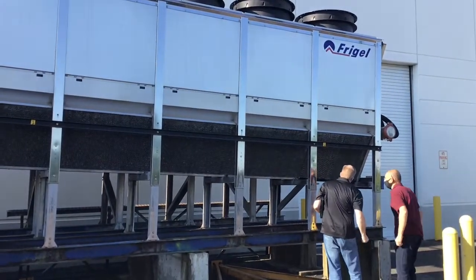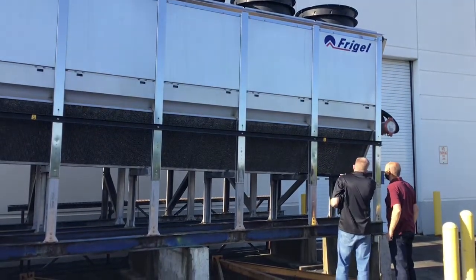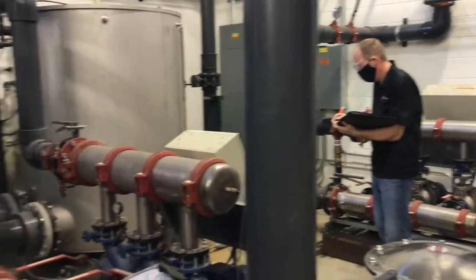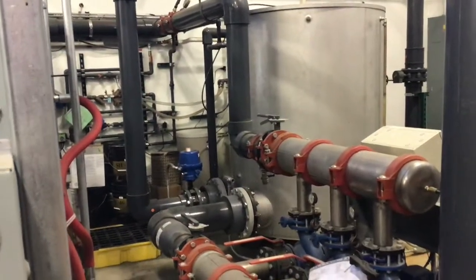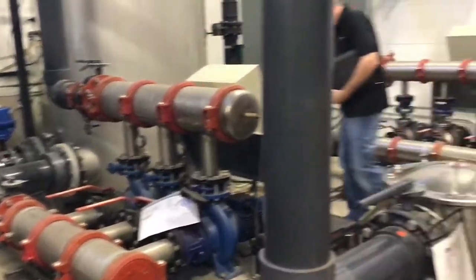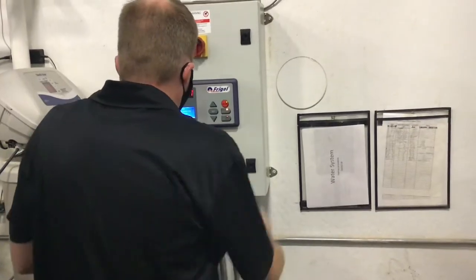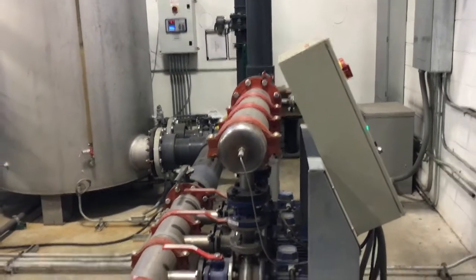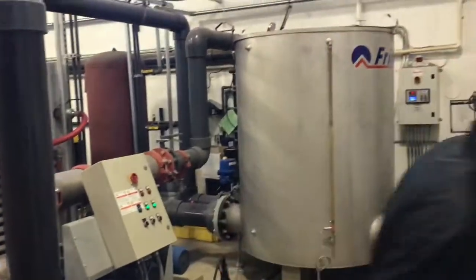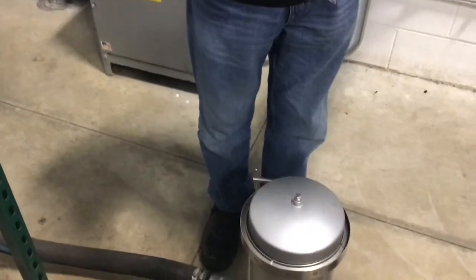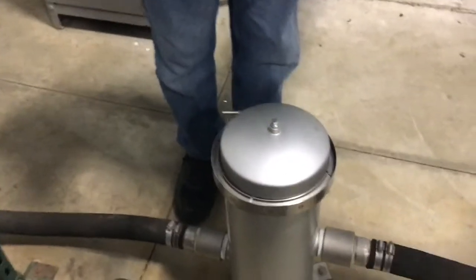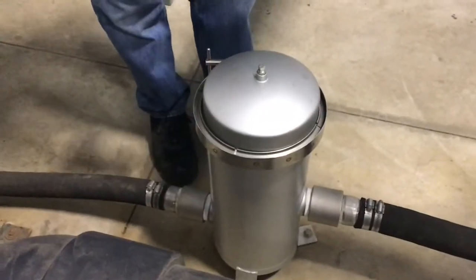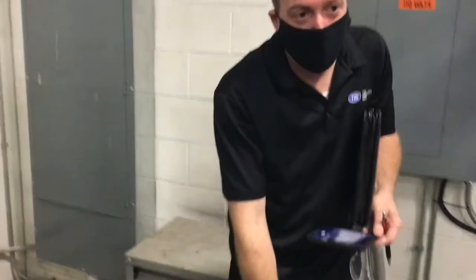As you're going through your system, whether that be on a quarterly, monthly, bi-yearly, or yearly basis, you're going to want to make sure and check all valves, all connections. You're going to want to check your control logic. You're going to want to check your thermocouples, make sure all those systems are operating correctly. And then you're going to want to also look at your valve systems on each filter. Meaning, do you have a bypass? Do you have an alarm? Do you have the ability to tell the difference when the PSI is starting to rise within a filter, on when to change that filter or that filter element?